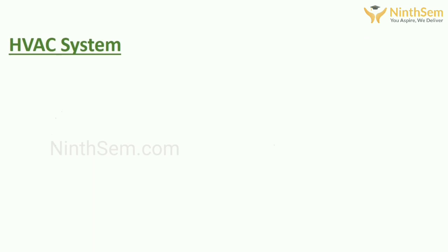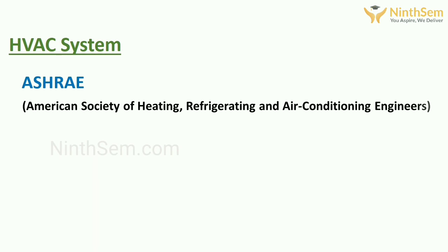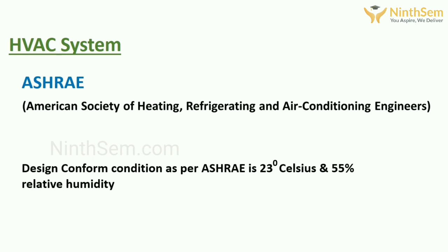HVAC system is designed based on ASHRAE, that is American Society of Heating, Refrigerating and Air Conditioning Engineers. The design comfort condition as per ASHRAE standard is 23 plus minus 2 degrees Celsius and 55% relative humidity.